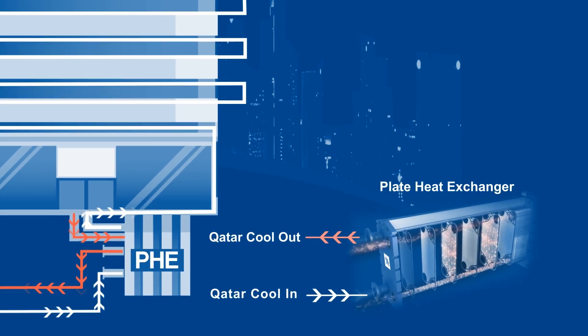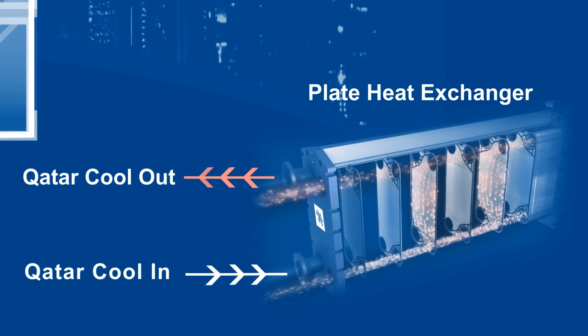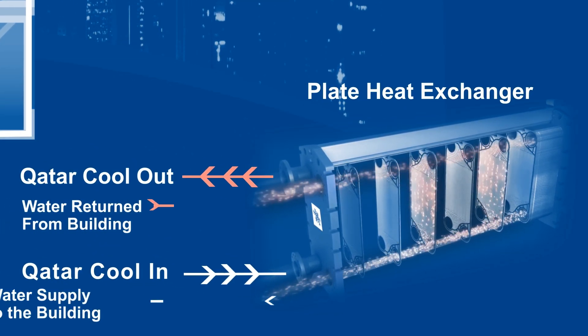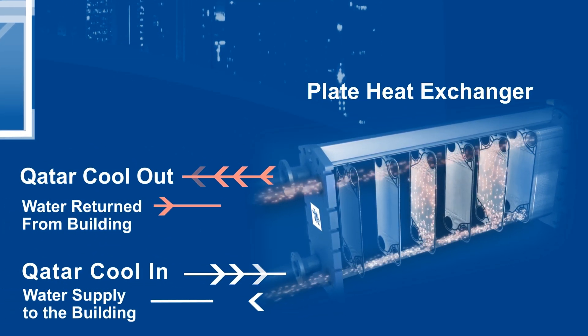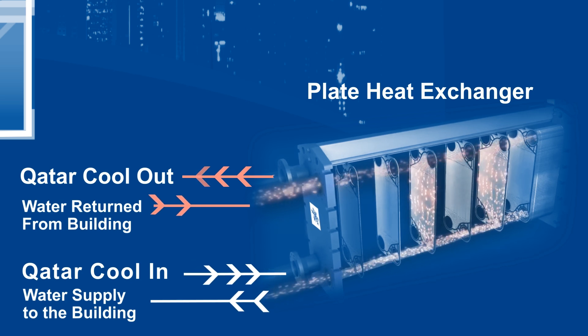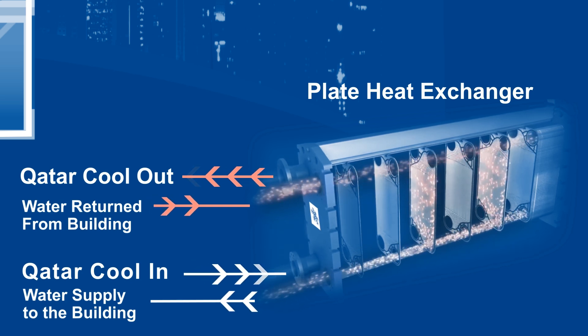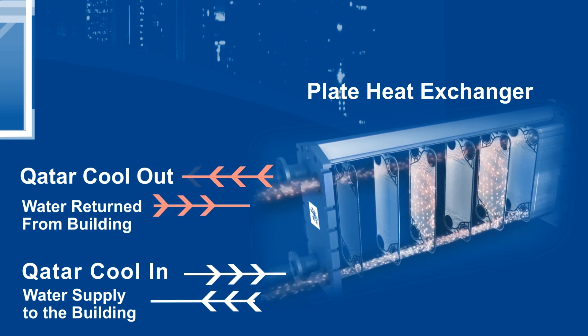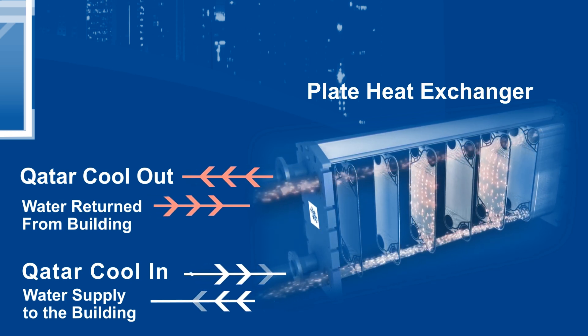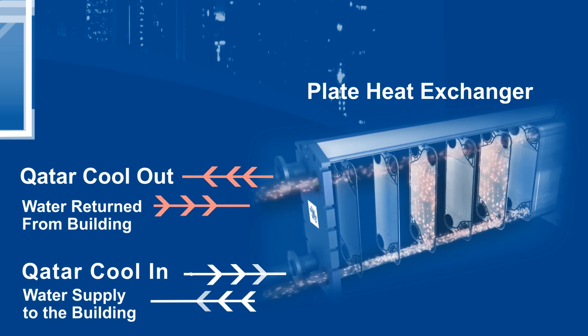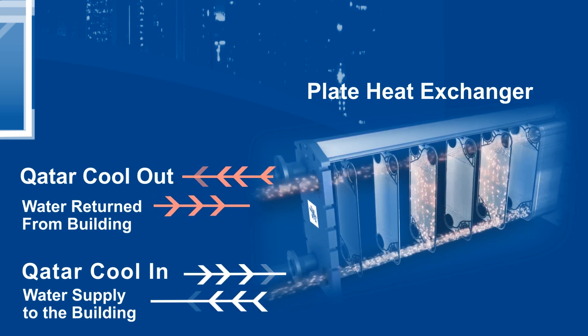The chilled water flows between the plates, separating the plant's water from the building's water, which is pumped through the building pipes into the fan coil units, where fans push the air against the coils, cooling the air and pushing it into the room.